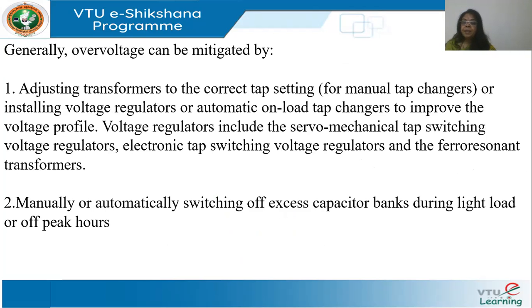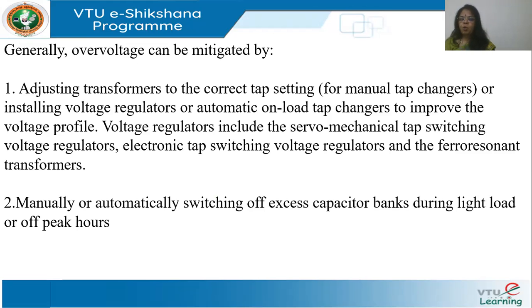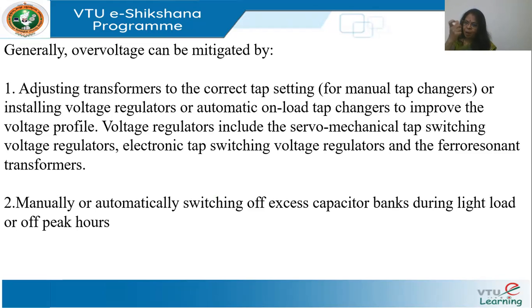To mitigate over voltage: first, adjust transformers to the correct tap setting. If you have automatic transformers, this can be done automatically. You can also introduce automatic on-load tap changers which will automatically reduce the tap if there is an over voltage, improving the voltage profile. Voltage regulators using mechanical or electronic tap switching are another option.